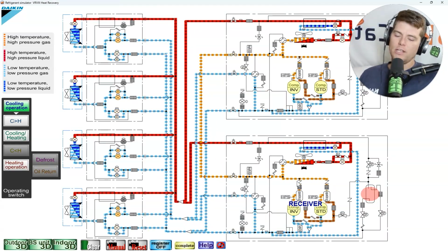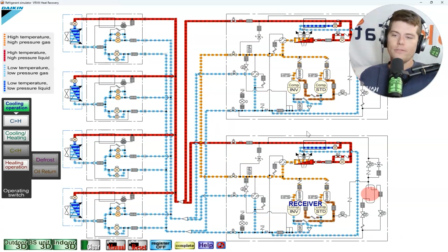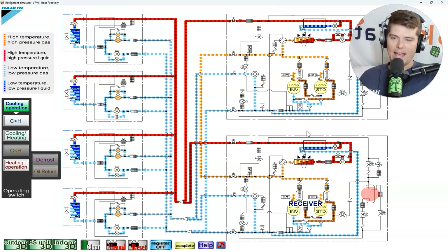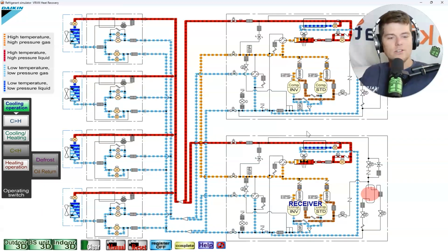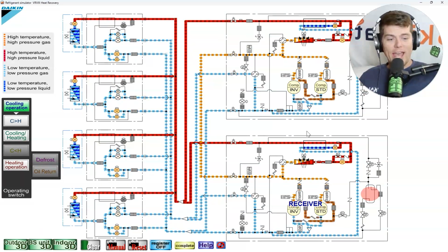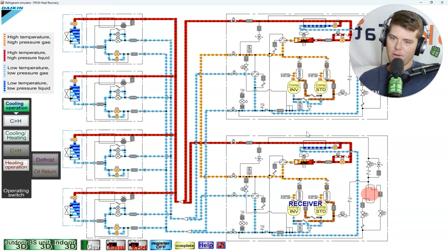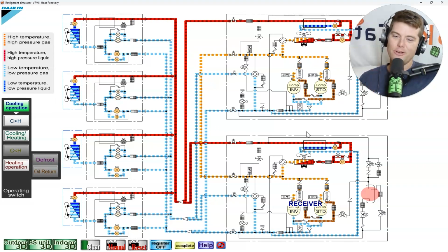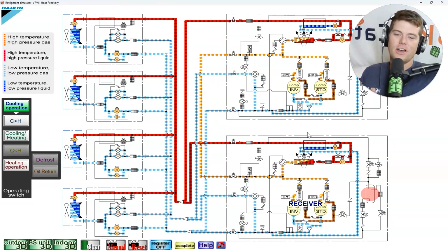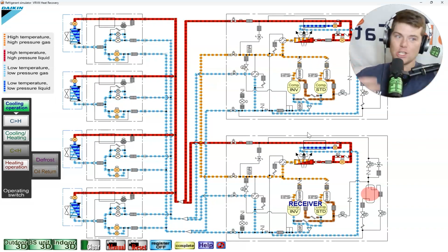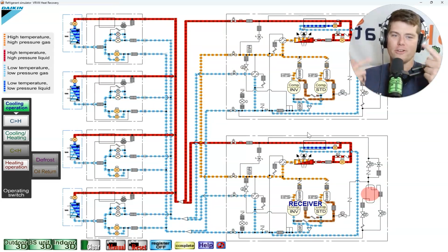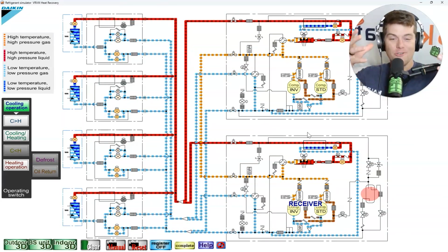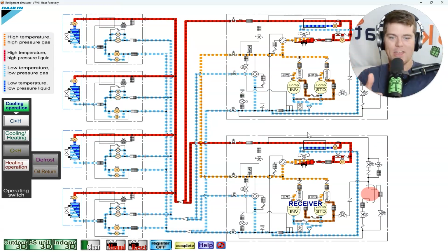Because remember, when we have 20 tons of cooling, let's say two 10-ton modules, upper and lower here, master and sub, you have to remember that we have 20 tons worth of capacity, 20 tons worth of compressors. An inverter and a standard, and an inverter and a standard. 4 compressors, right? With the 4 compressors that we have here, we have 20 tons of capacity. So what do you need? You need 20 tons of refrigerant to move that capacity. It's not just enough to spin compressors at 20 tons worth of capacity and move refrigerant super fast. You have to have the refrigerant quantity to move that many BTUs.